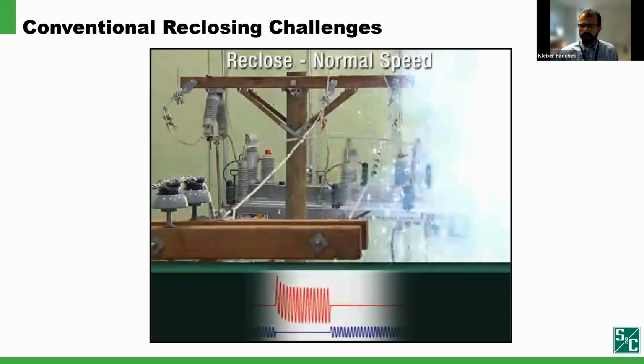Here's a video of a test performed in our lab in Chicago, showing how conventional reclosers test for fault presence. You see a phase-to-phase fault situation, where a wire is created across the conductors there. And the device that's testing for the fault is set for 2 fast operations followed by 2 slow operations. That's why there is increased time in the interval between the reclosing activities. As I show the video, please be advised that the sound of the reclosing activity will be very loud, so please be prepared for it. If you're using a headset, I'd suggest that you move the headset away from your ears. So here we go.